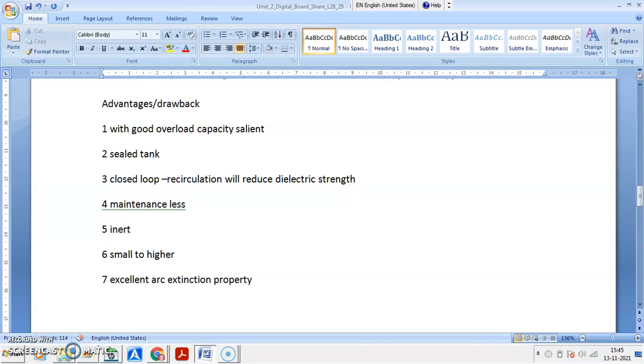Some things we have considered: sealing of the tank is also a problem. You need a special material for sealing of the tank. You should not allow leaks, you should not allow moisture to enter inside the circuit breaker tank or the circuit breaker arc extinction chamber. So as far as the SF6 gas circuit breaker is concerned, these are two types of SF6 circuit breaker: the SF6 double pressure with tank circuit breaker and the puffer type SF6 gas circuit breaker. Okay.